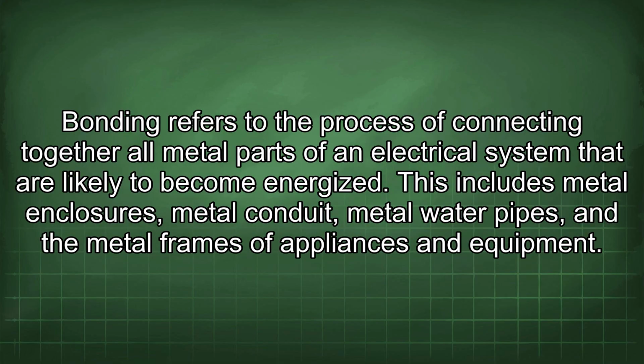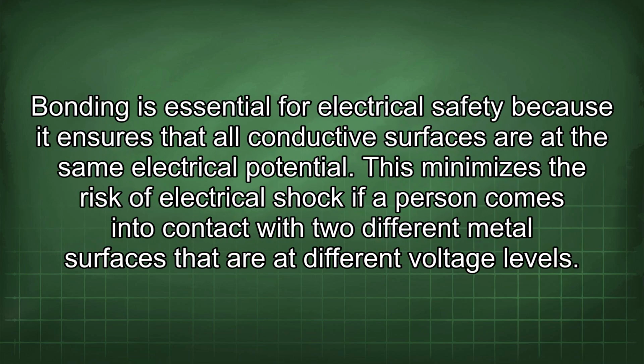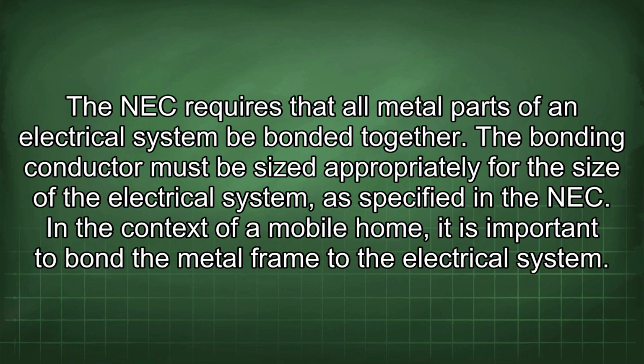Bonding refers to the process of connecting together all metal parts of an electrical system that are likely to become energized. This includes metal enclosures, metal conduit, metal water pipes, and the metal frames of appliances and equipment. Bonding is essential for electrical safety because it ensures that all conductive surfaces are at the same electrical potential. This minimizes the risk of electrical shock if a person comes into contact with two different metal surfaces that are at different voltage levels. The NEC requires that all metal parts of an electrical system be bonded together. The bonding conductor must be sized appropriately for the size of the electrical system, as specified in the NEC.